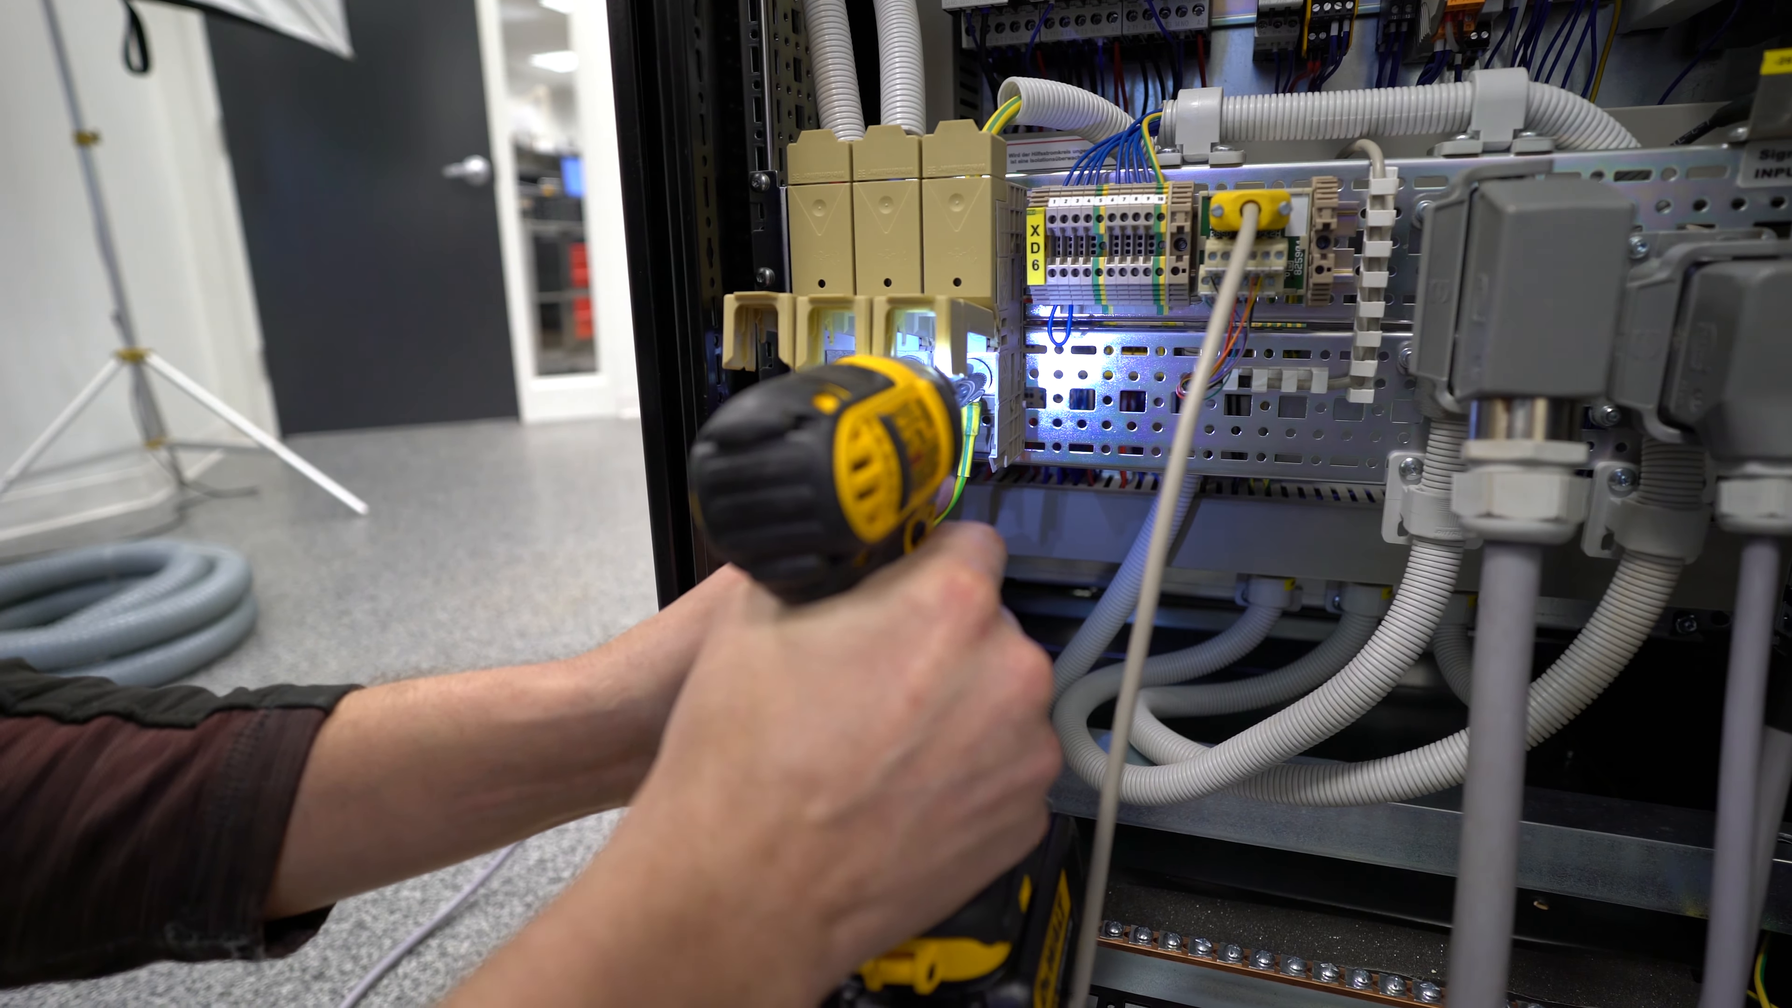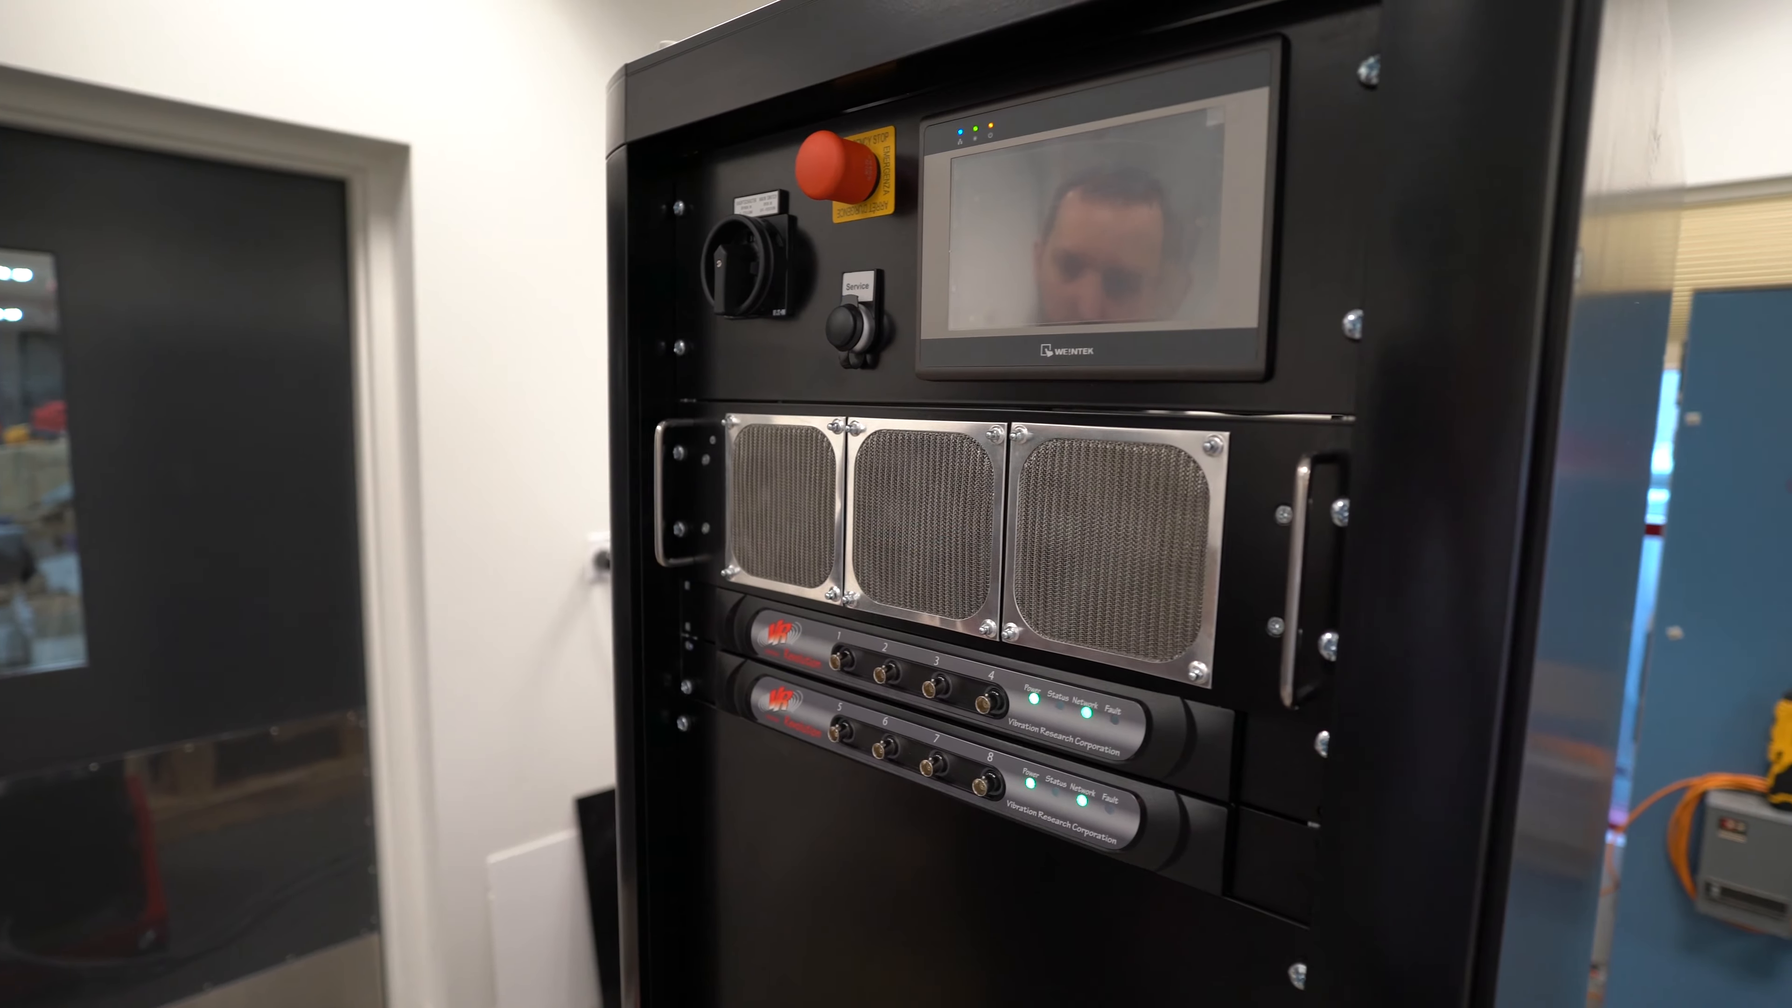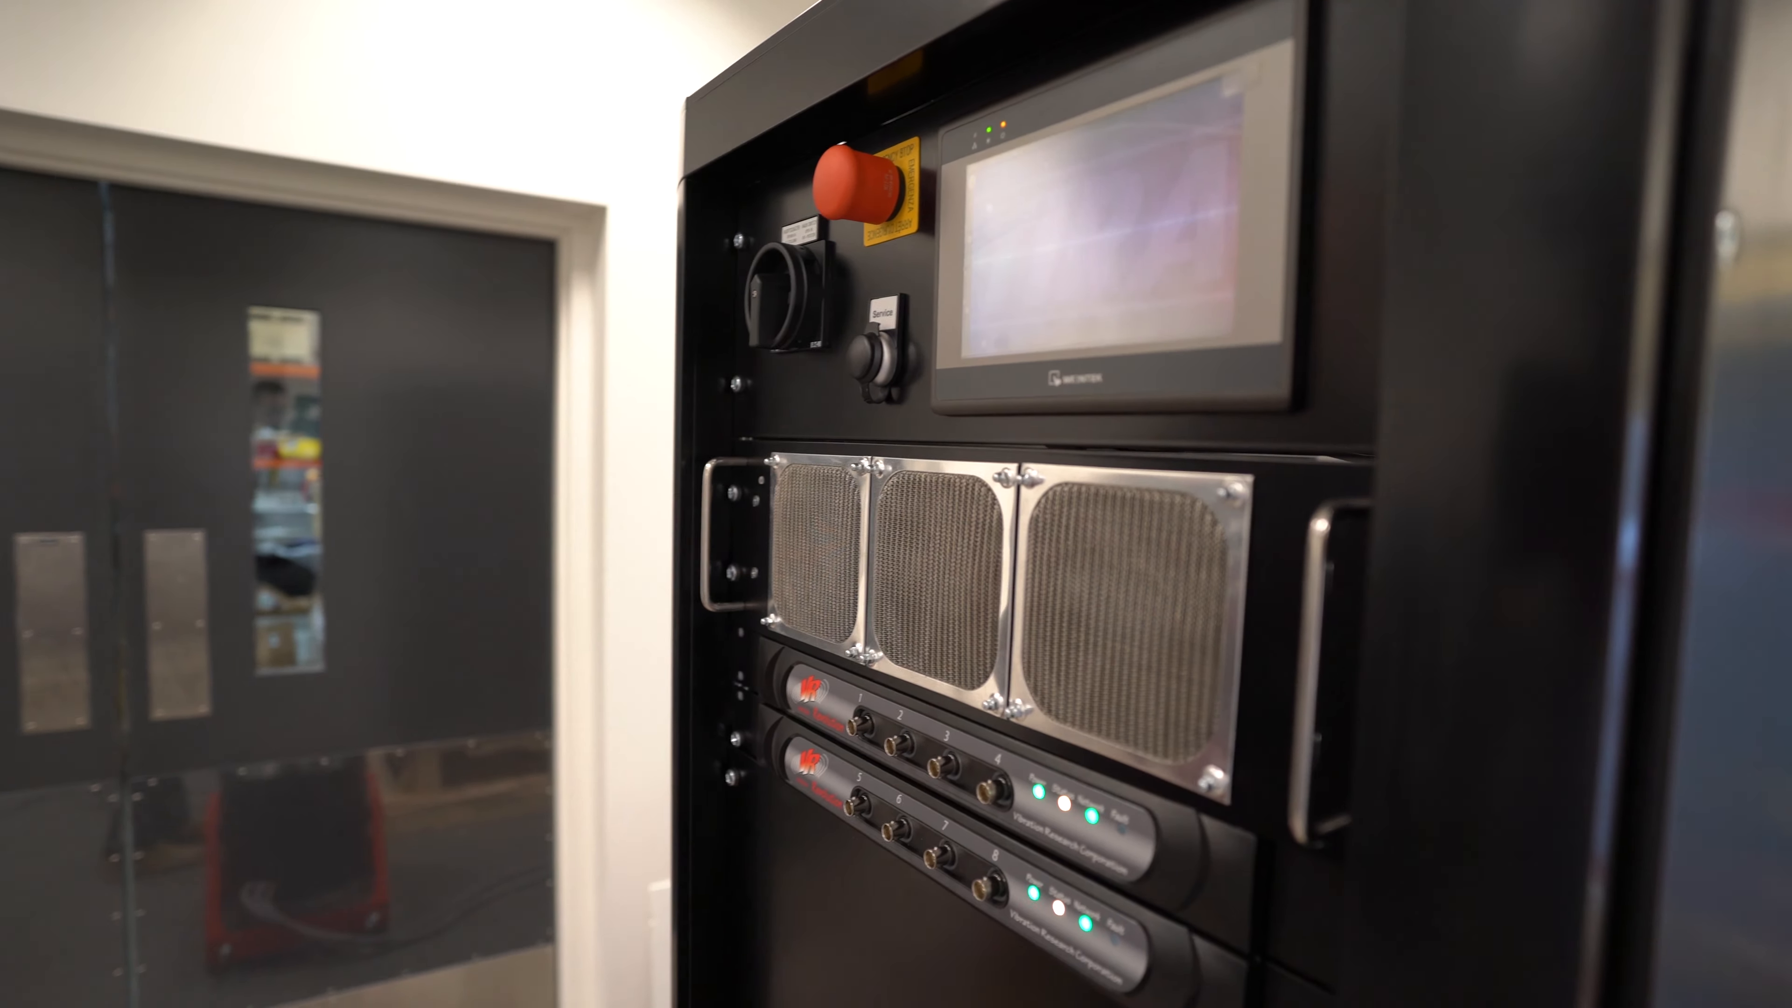Now that we've got everything connected on the backside of the controllers and the network switch installed, we can go ahead and power up the system. We've got the big turn switch here. Rotate 90 degrees clockwise and you'll see the auxiliary power will turn on. Your 9500 controllers will power up and you'll start seeing some display on the touchscreen interface.